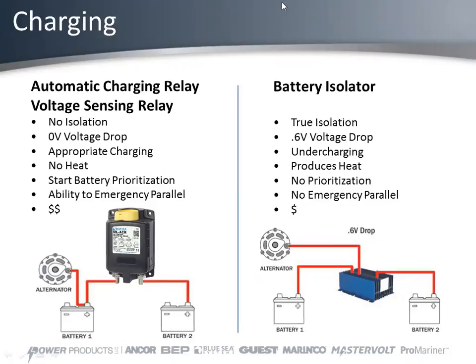Who's familiar with an ACR? It's basically a voltage-sensitive relay, or automatic charging relay, that senses the battery bank side. As soon as it sees the voltage increase over 13.7 volts, it closes that contactor, allowing the second battery to come online and charge at the same time. So you start the engine while the two batteries are completely separated, and as soon as there's a charge current available, the two batteries are tied together.